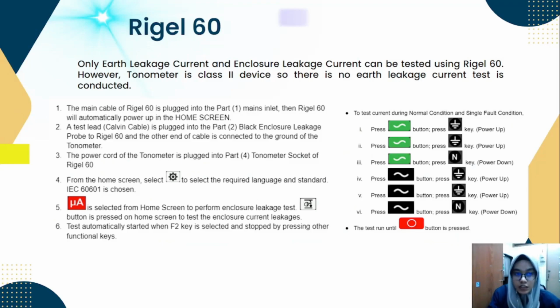Next, for the Rigel 60, only earth leakage current and enclosure leakage current can be tested. However, because the tonometer is a class 2 device, no earth leakage current test is conducted. First, the Rigel 60 is plugged in and it will be automatically powered up. Then a test lead is plugged into the black enclosure leakage probe of the Rigel 60 and the other end of the cable is connected to the ground of the tonometer. Then the power cord of the tonometer will be plugged into the socket of the Rigel 60.